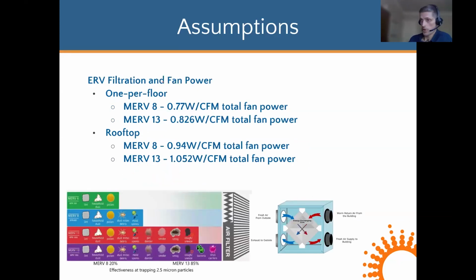We also looked at filtration, and 2 filtration levels we wanted to study, the MERV 8, which is essentially the code minimum, and then an upgrade to MERV 13, which comes with an increase in static pressure. So we wanted to look at how the fan power varied for the 1 per floor unit and the rooftop units. We did also want to look at reduced ventilation flows to meet the passive house balanced ventilation levels to see how this could affect energy consumption as well.